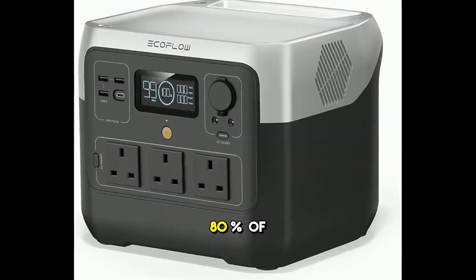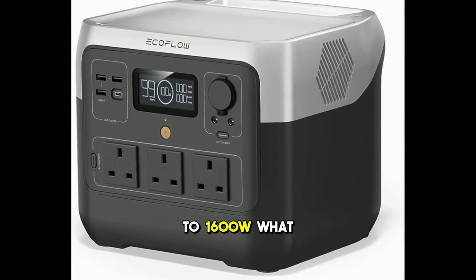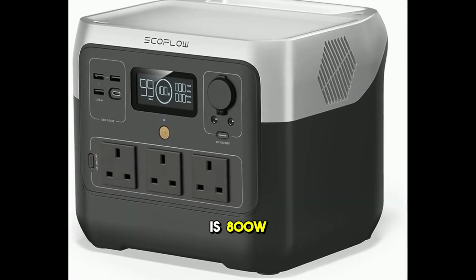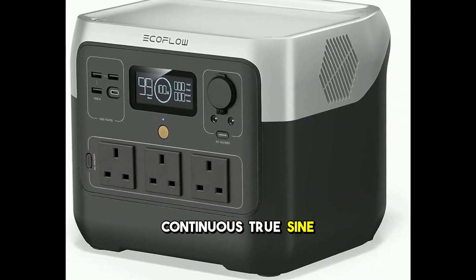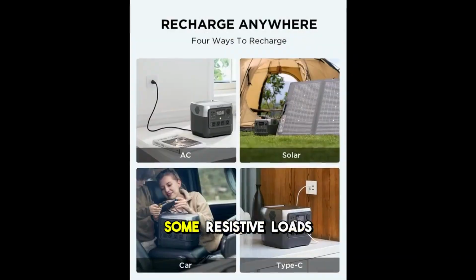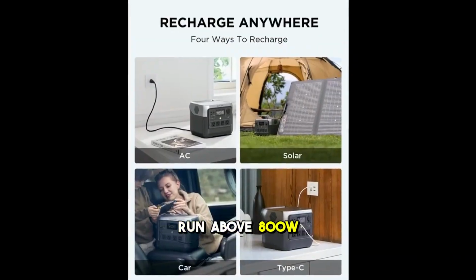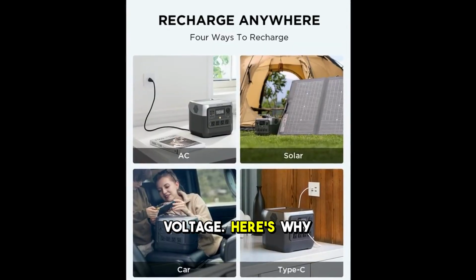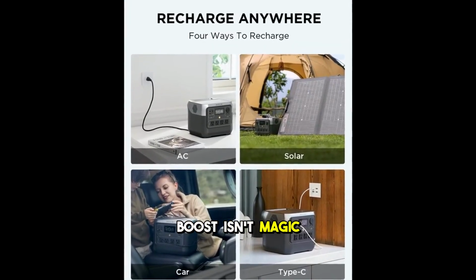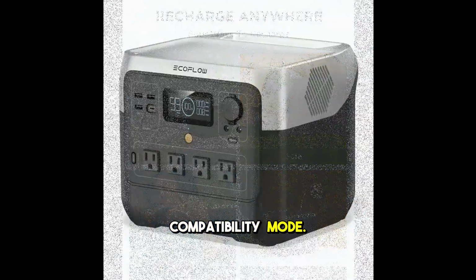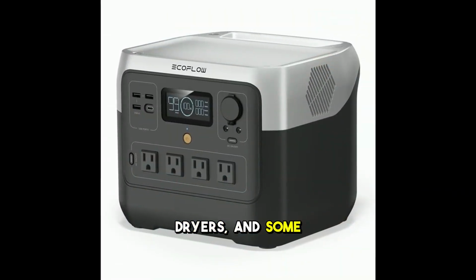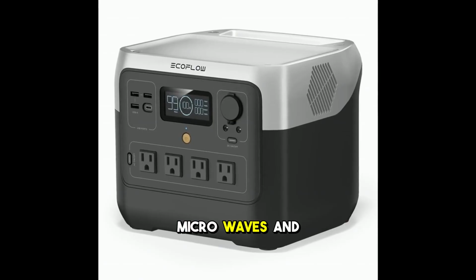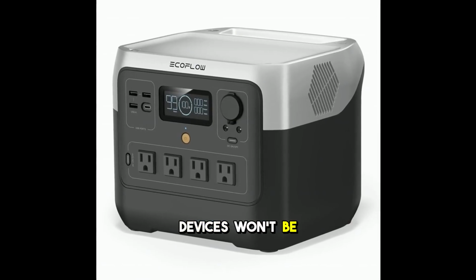They claim to power 80% of appliances with up to 1600 W. What you actually get is 800 W continuous true sine wave, and X-Boost that lets some resistive loads run above 800 W by lowering voltage. Here's why that matters: X-Boost isn't magic watts, it's a compatibility mode. Space heaters, hair dryers, and some tools may run, but microwaves and many motor compressor devices won't be happy, and sensitive electronics might misbehave.